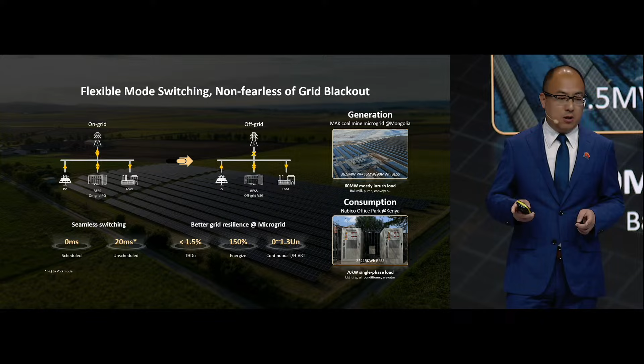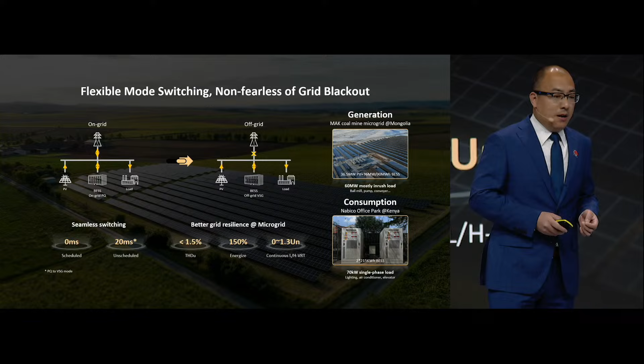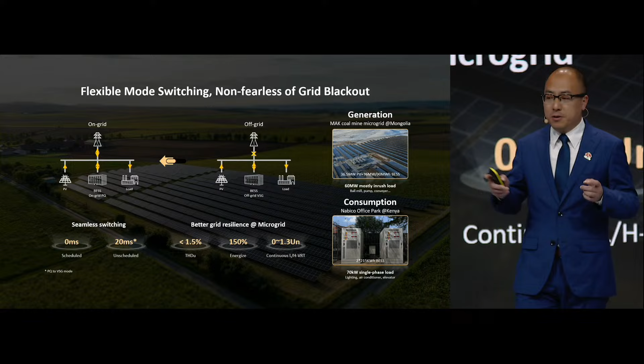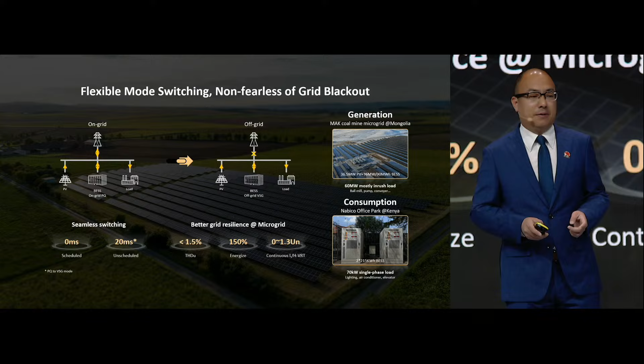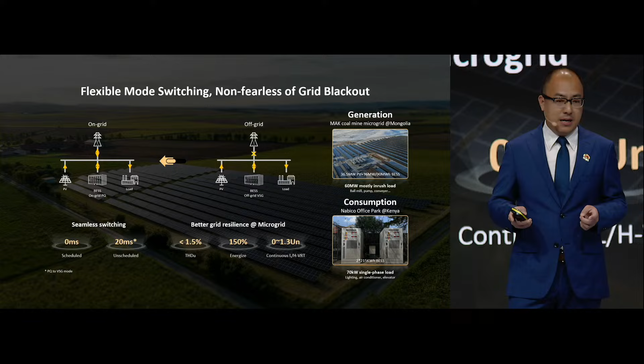In Mongolia, at the mining microgrid, the system is delivering improved grid resilience after microgrid conversion. The THDU is below 1.5% by active harmonic suppression technologies. The system can also handle 1.5 times the transformer inrush current and continuous ride-through from 0 to 1.3 times rated voltage for improved microgrid stability. When the main grid fails, critical loads can operate stably in off-grid mode.